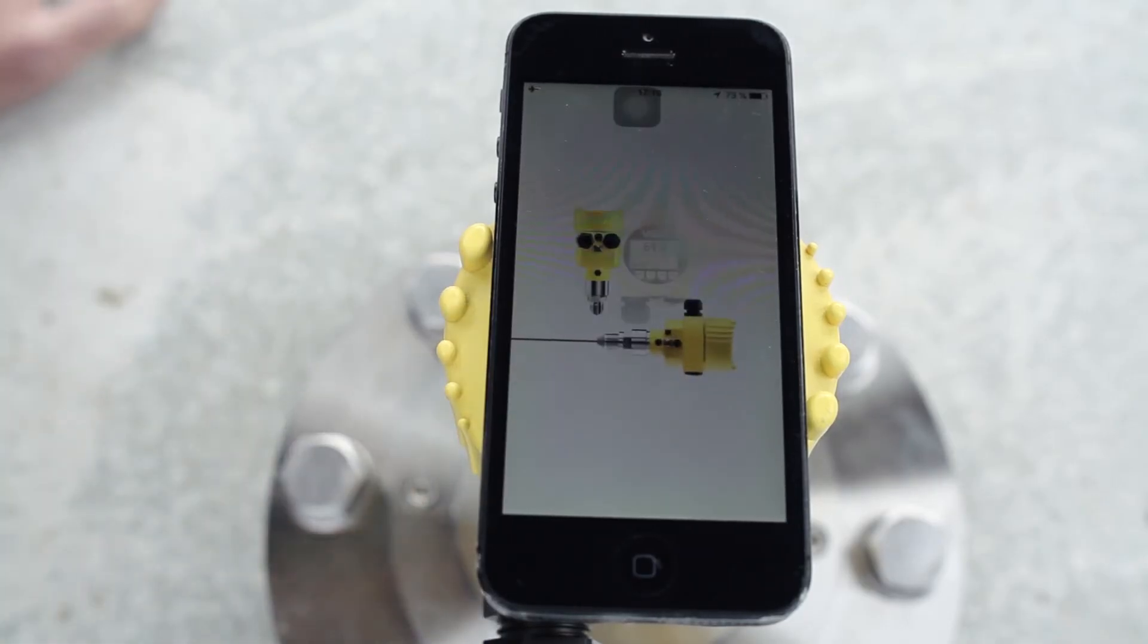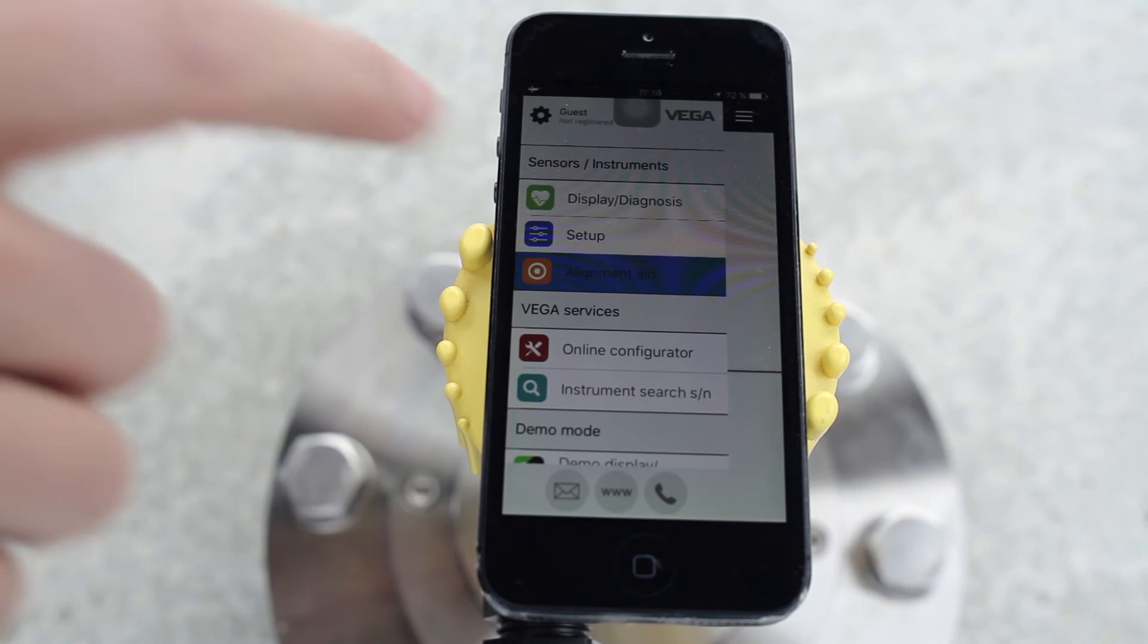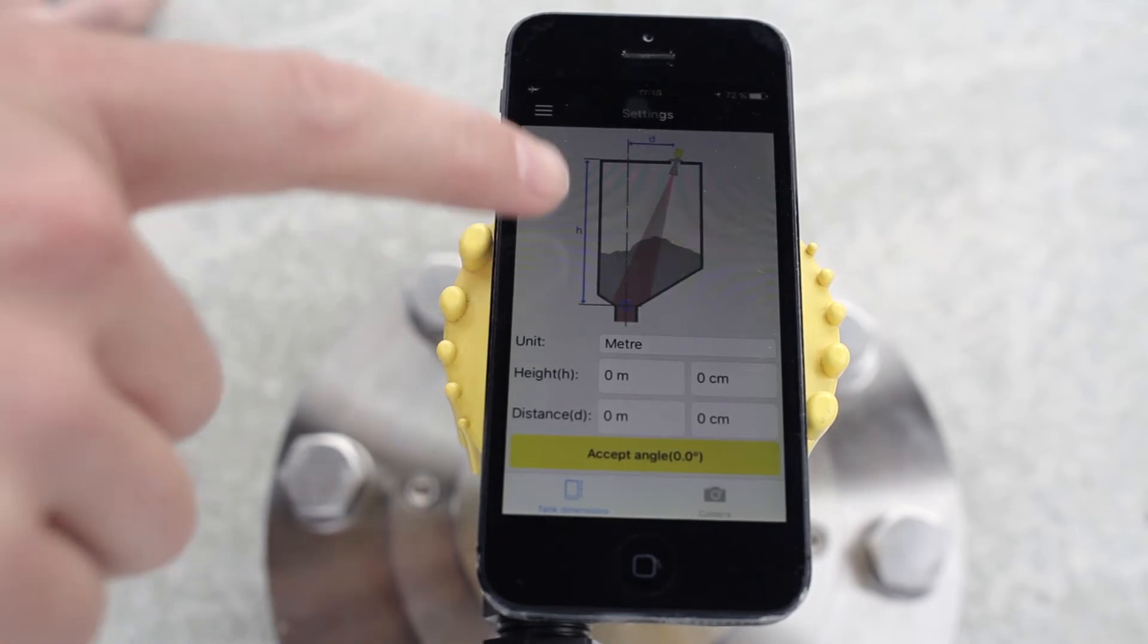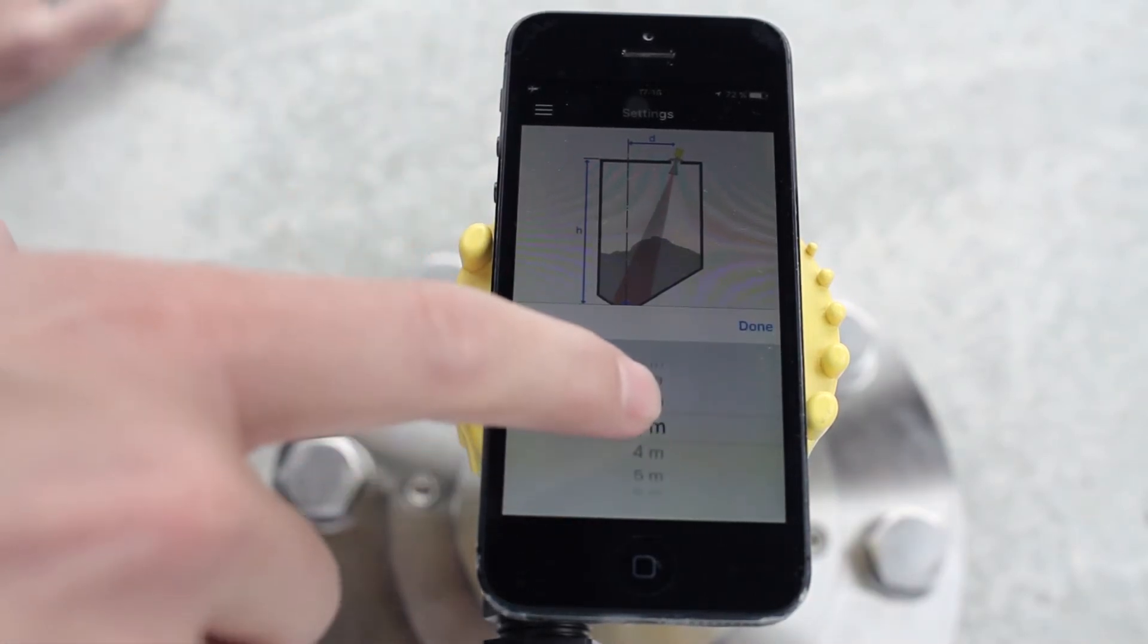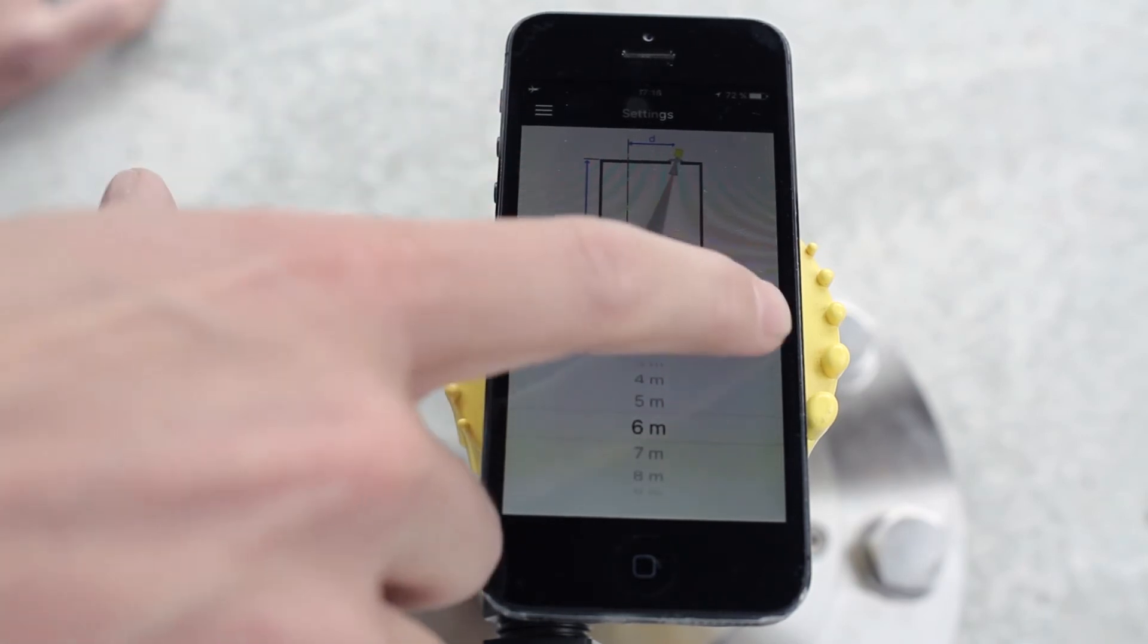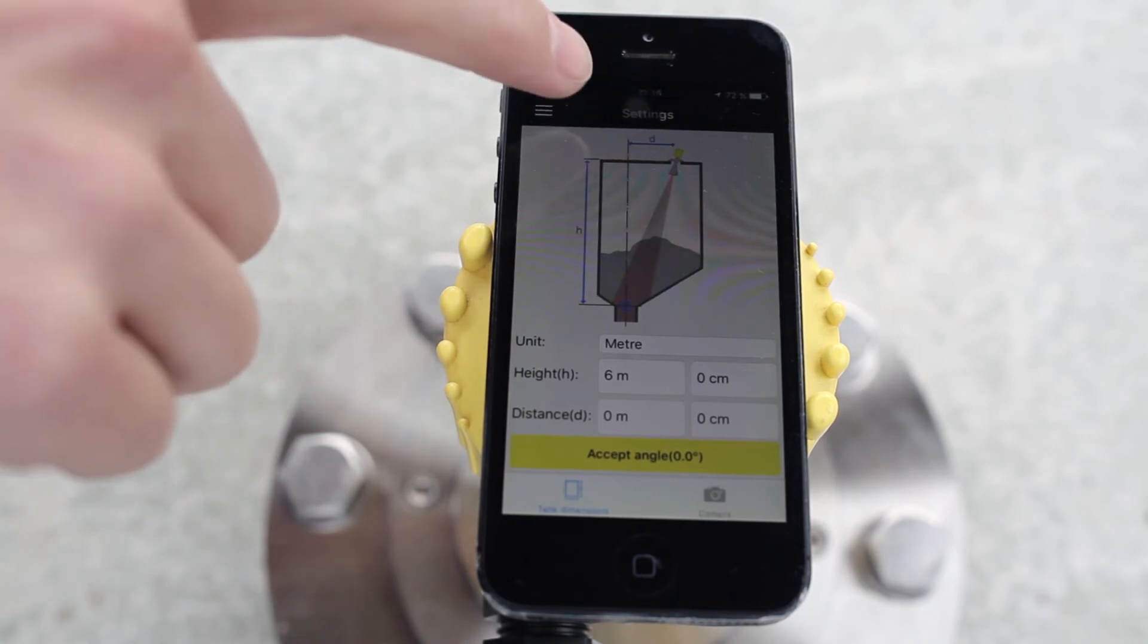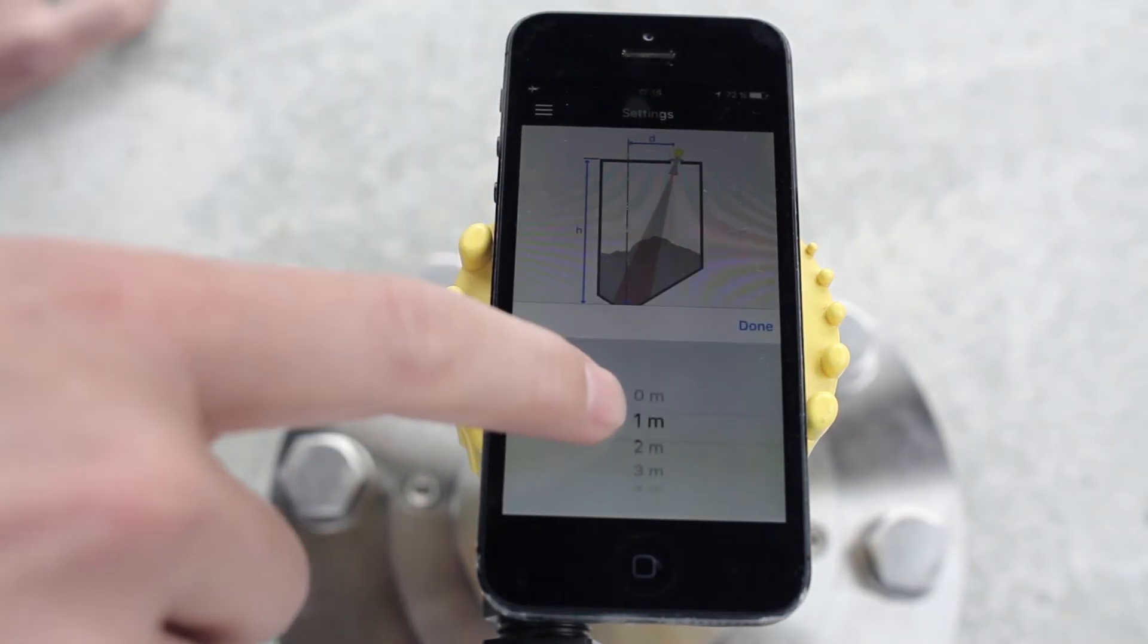In the Vega Tools app you find the alignment aid. With this alignment aid you can make the adjustment very easy. You need the height of the silo—in our case it's about six meters—and then you need the distance from the sensor position to the outlet of the silo. In our case, 1.25 meters.